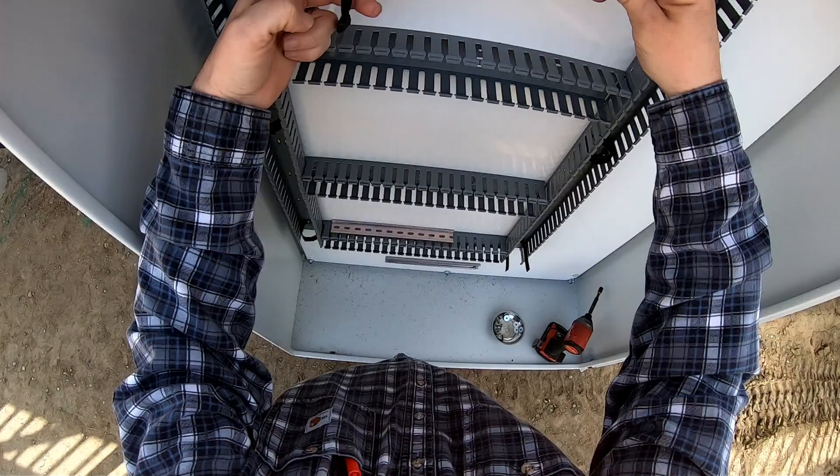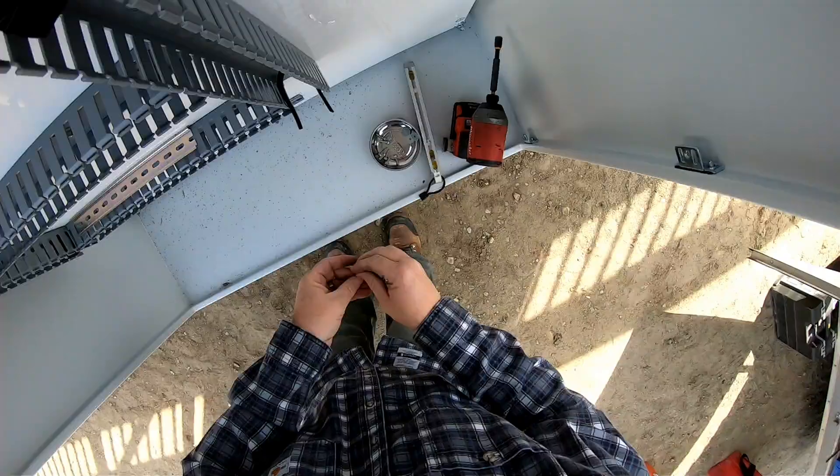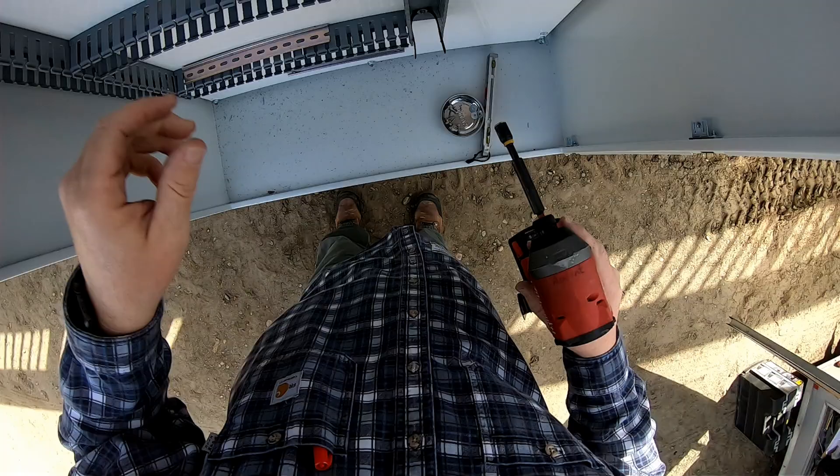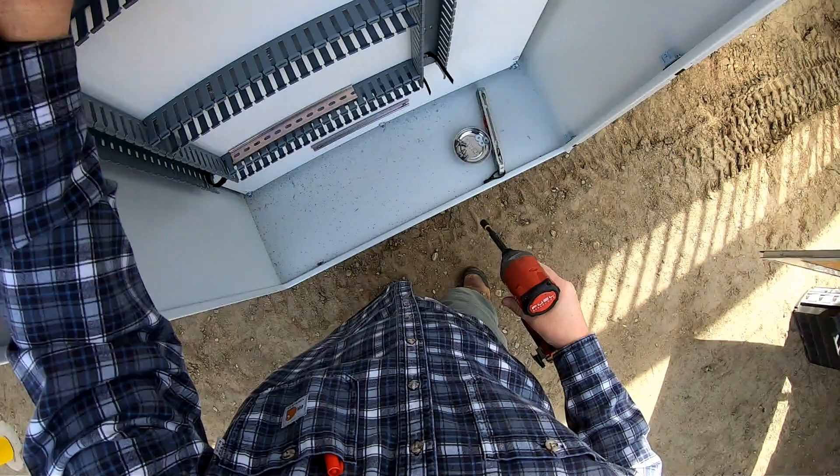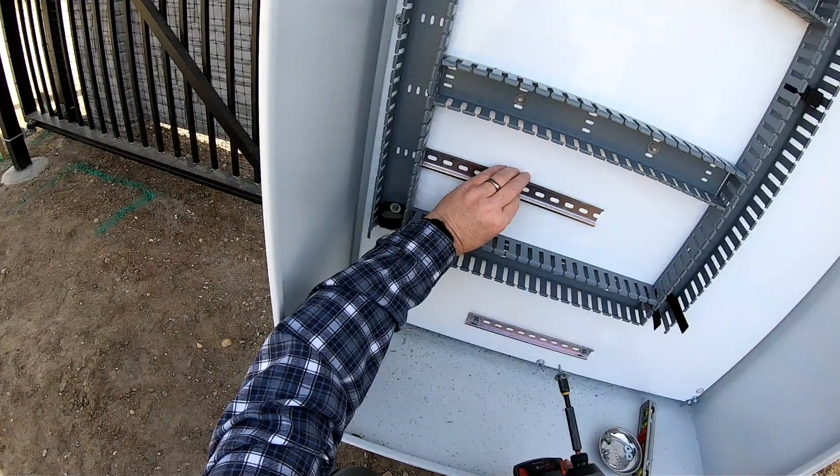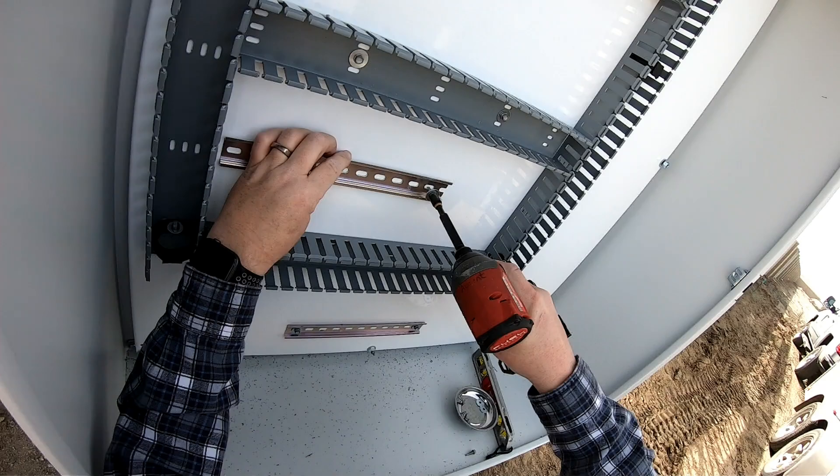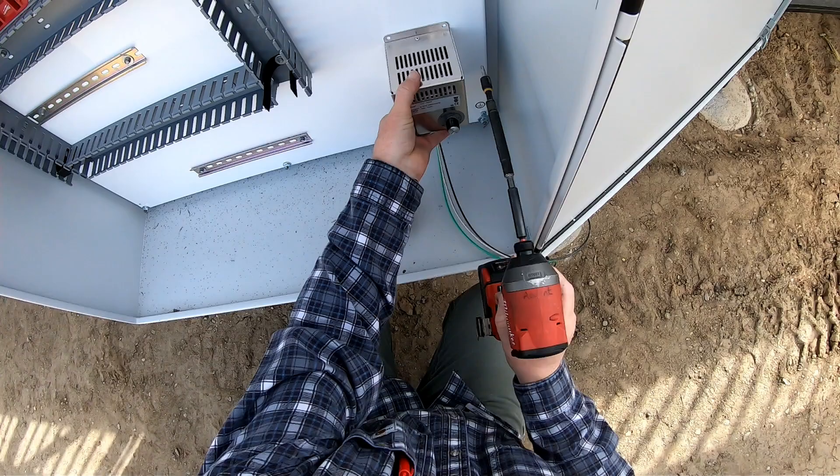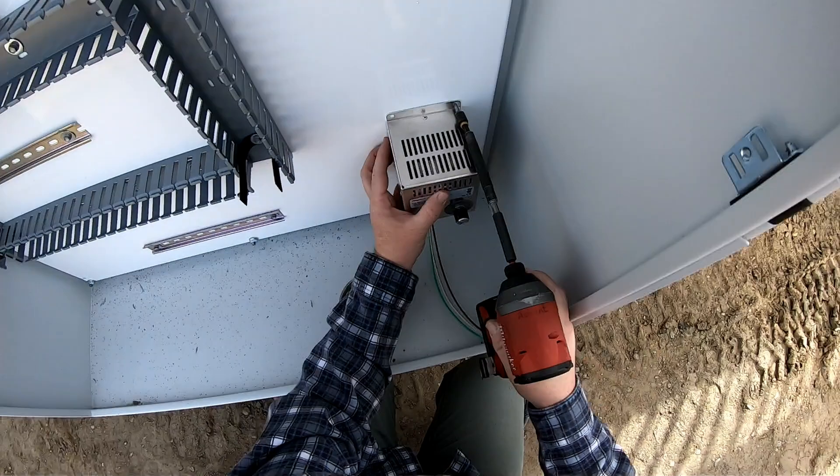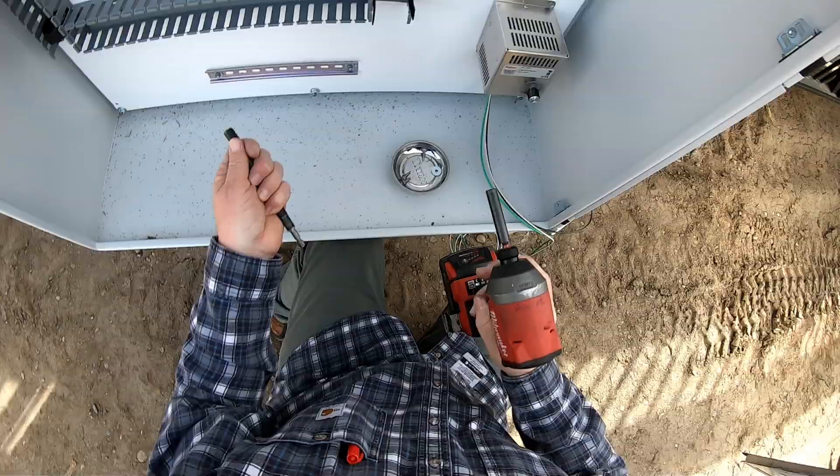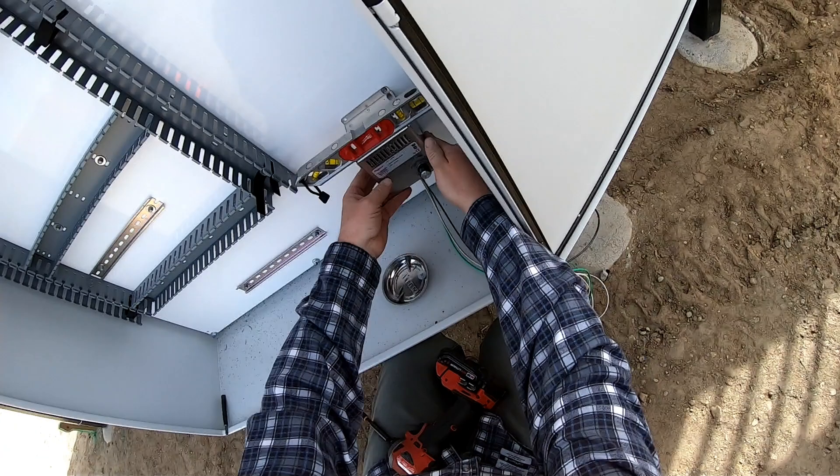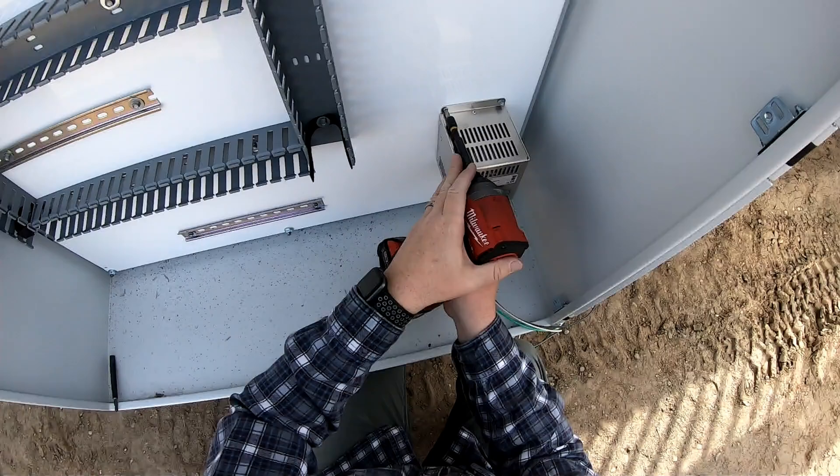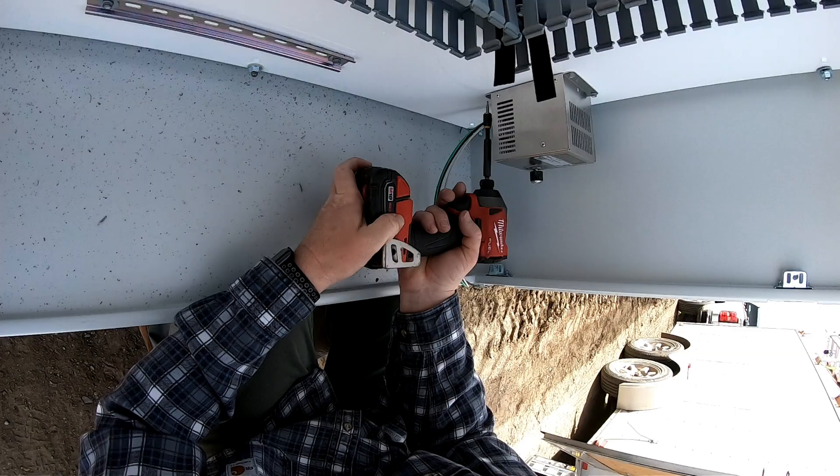Here I am mounting it. I like to use those same Tek three screws, self-tapping screws, and I like to put a washer in there too. We put a pretty big Cisco switch on here. Not that big, but I don't want that din rail falling off. Now I've moved on to installing my heater. I like to get this thing pre-wired too. It's kind of hard to get your tweaker up in there to feed those wires in after the fact.